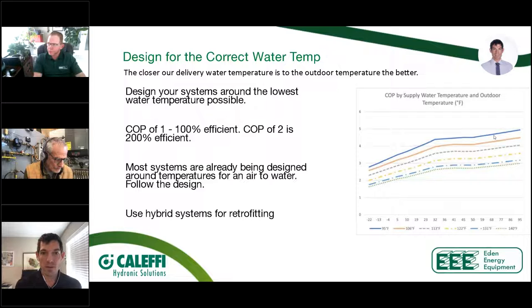It's funny how different manufacturers show this information, but the higher we're trying to lift water with anything, with a boiler, a condensing boiler, a solar panel, a heat pump, whatever it is, if you're trying to take water up to 140 degrees in this graphic, the efficiency of that appliance is going to suffer. So in COP, if we're moving 95 degree Fahrenheit water around to heat everything, we're going to see the best version, the LeBron James of performance of that equipment.